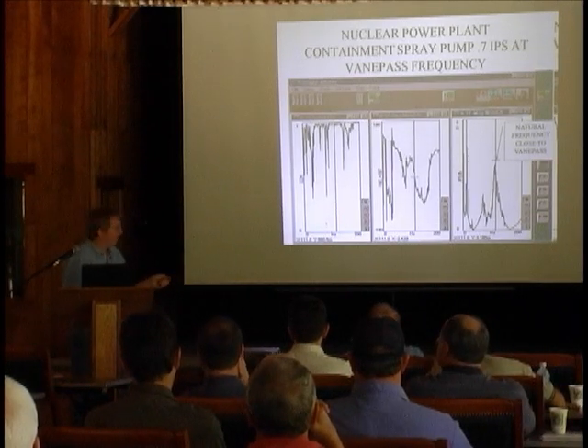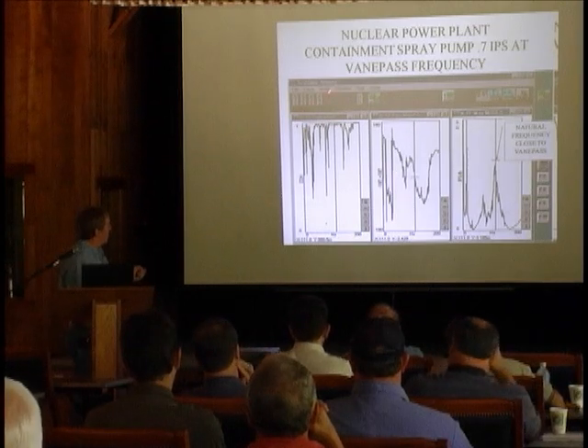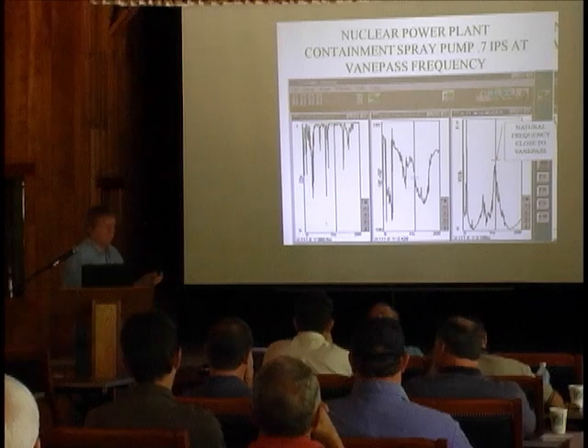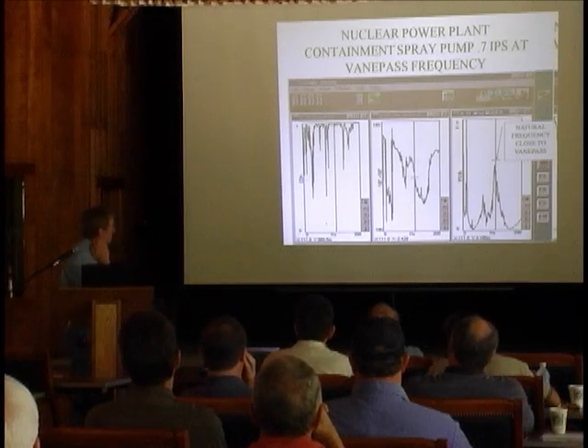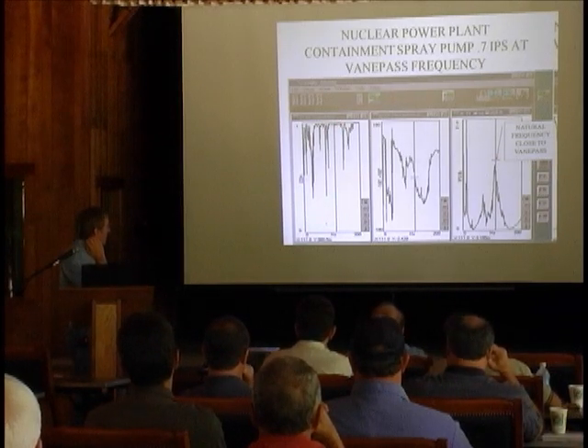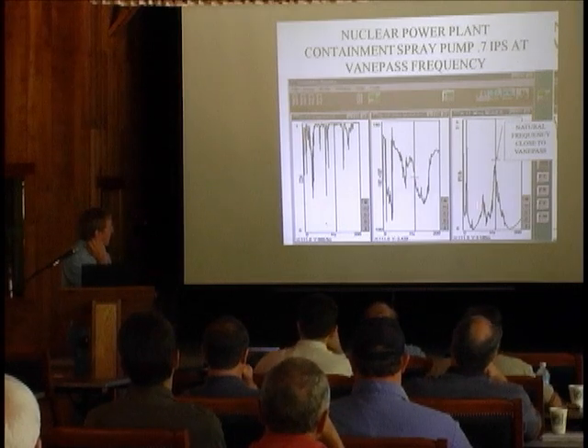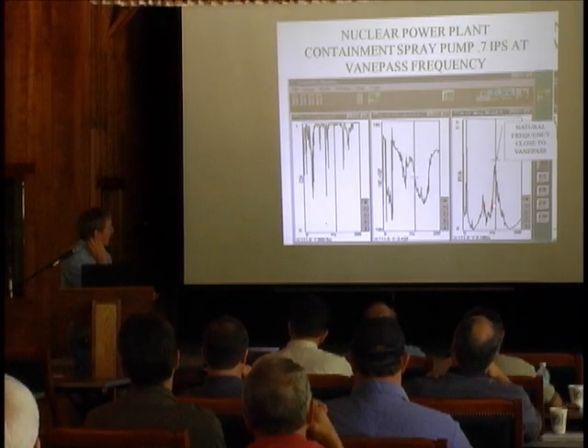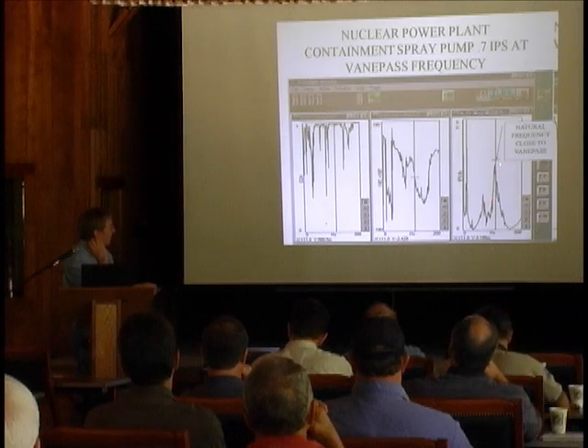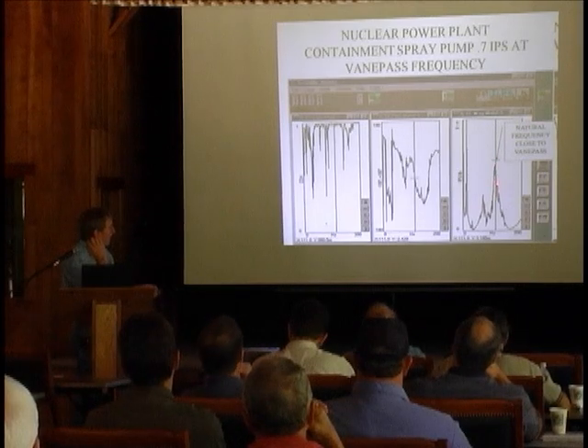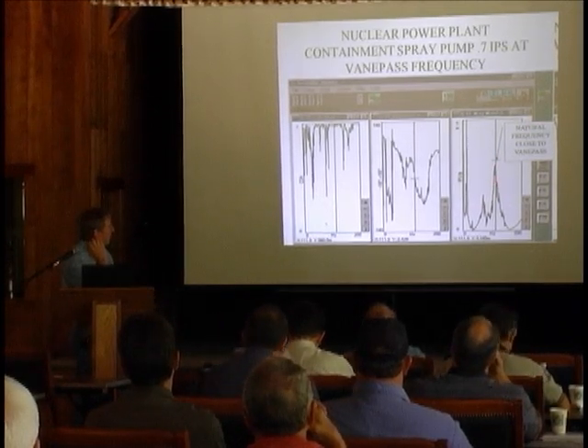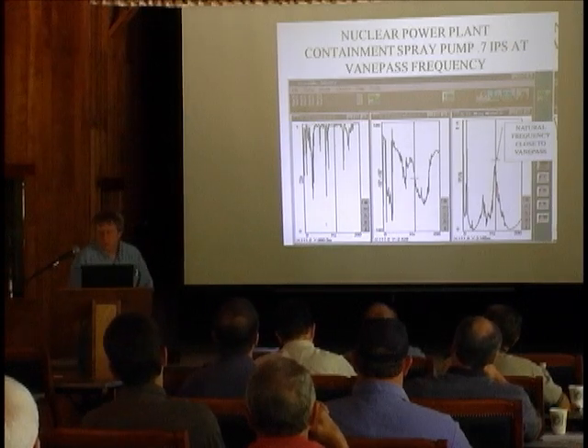But anyway, I did a resonance test on the pump. It's a vertical pump. Here's your coherence. Here's your phase shift. Here's your response. And we find a natural frequency pretty close to vane pass. This is 111, and the vane pass is here at about 118. So very, very close, as we suspected.